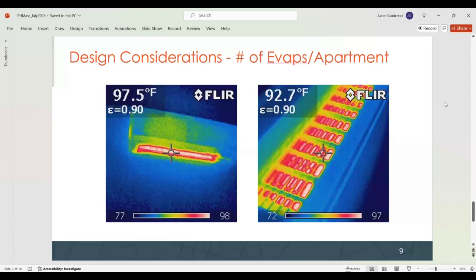So the deal is, if you have one person in a line of a VRF system that doesn't have energy recovery, everybody's going to get the most minimal amount of refrigerant that goes through that line. Everybody on that line is going to get it. So everybody on this floor, whether their thermostat was on or off, was getting this amount of refrigerant. And we kept wondering why the building was so hot.